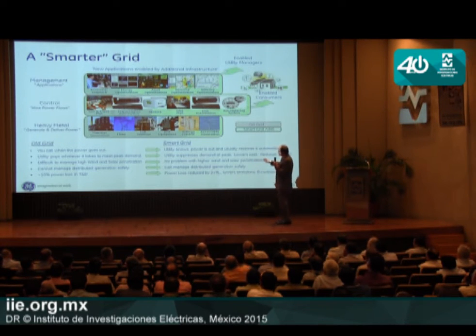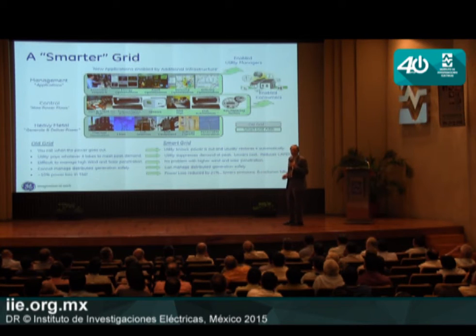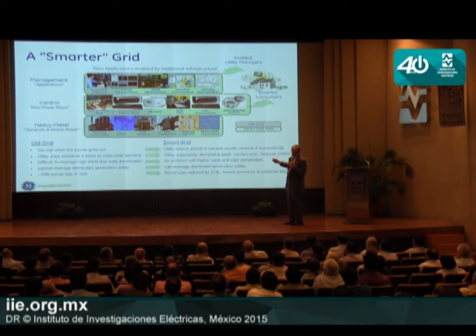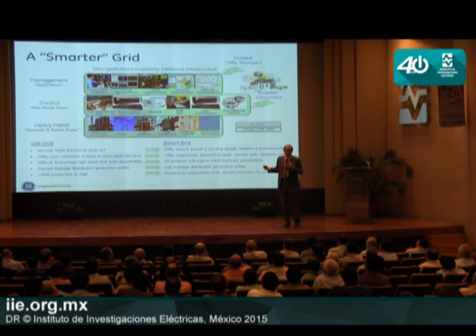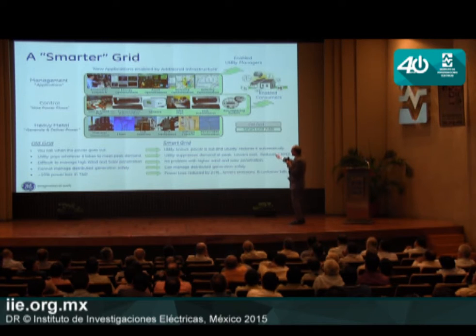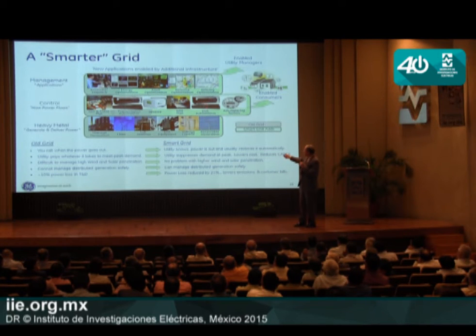So a lot of us are focused now on the distribution system, a separate SCADA system, a separate control system for distribution management, logic in the distribution substation. Like we said, in the US half of the distribution substations aren't automated, and then there's logic downstream of the substation on the feeders. This is the strongest business case today of any smart grid technology, right here.